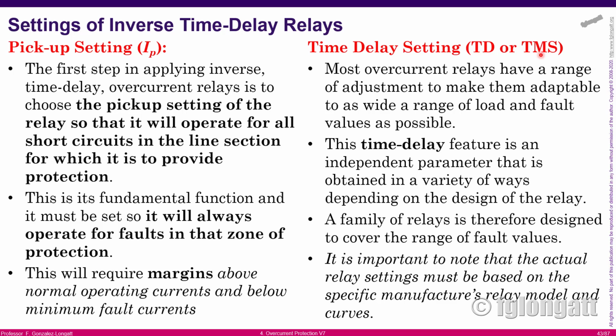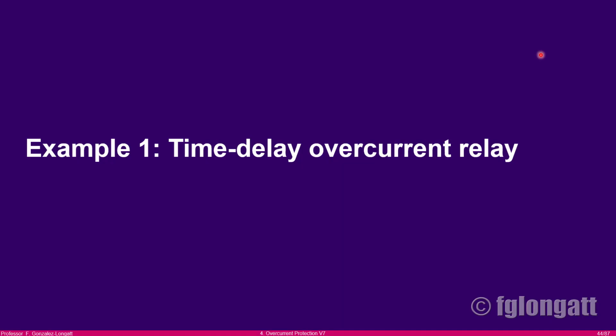American or European standards have different names, but it's the same, and they represent the characteristic that creates a family of curves that you can use for setting time delays between the curves and for making the coordination work. Okay. Right now I will go through one example, and this is example number 1 for the time delay overcurrent relay.